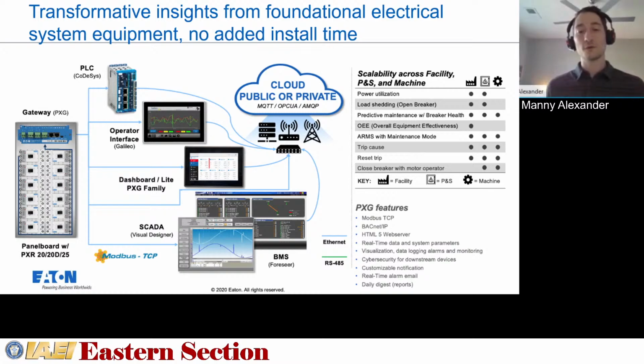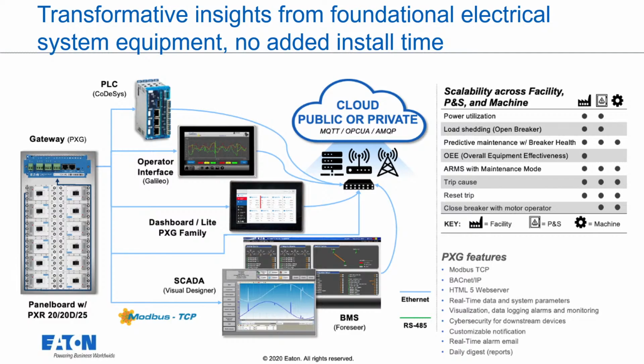So often, what we'll do from our factories is factory daisy chain those breakers together with the Modbus communications up to something, whether that's maybe a Power Xpert gateway where you can connect to a PLC, an operator interface like Galileo, or maybe instead of a gateway, you might use the Power Xpert dashboard lite processor, which is really cool because it basically compiles all of that great data that the PXR trip units are collecting and presents it in a very intuitive dashboard that gives you the ability to not only look and pull at the data with that interface, but also click on the devices and maybe load set points remotely or activate ARMS remotely when you're outside of that arc flash boundary.